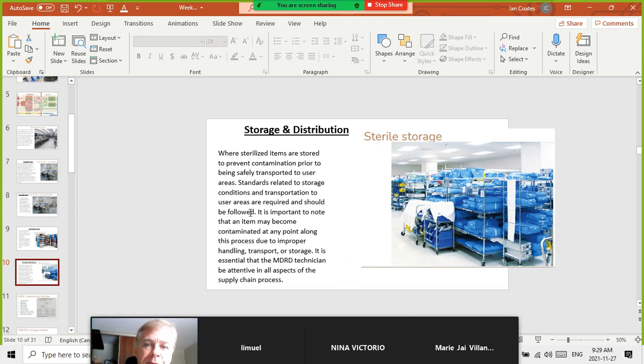Storage and distribution, where the sterilized items are stored. Okay, and again, in the decontamination area, there's a negative pressure. Here we've got basically a positive pressure. You've got the pressure emanating from here. So the airflow is coming from here because it's clean air, and that's where we want to spread the clean air. We don't want to spread the dirty air. Standards related to storage conditions and transportation to user areas are required and should be followed.